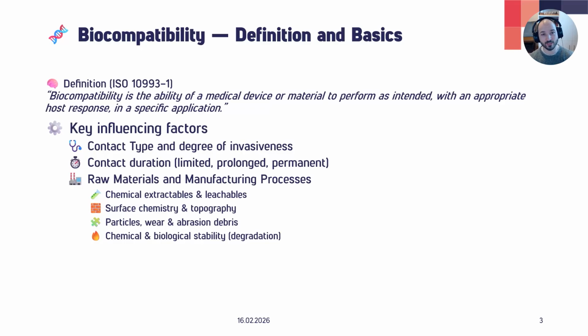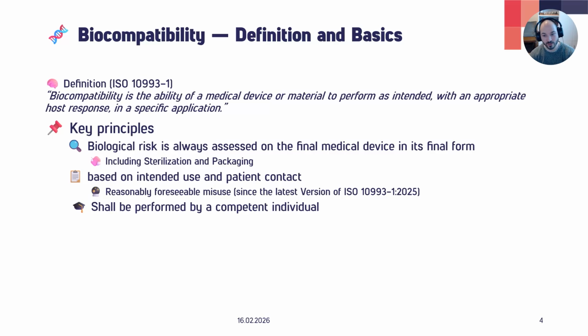And the key influencing factors, as I said, are the invasiveness and the contact duration. And the third thing is going to be the raw material and manufacturing processes that go into here. So it's the extractables and leachables, what kind of chemicals can leach out of the material, the surface chemistry and topology, but also particles and wear, and the chemical and biological stability. Then what's also very, very important is that the biological risk is always assessed on the final device in its finished and final form, so including sterilization and packaging.